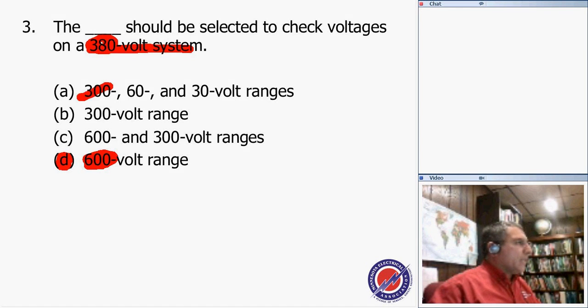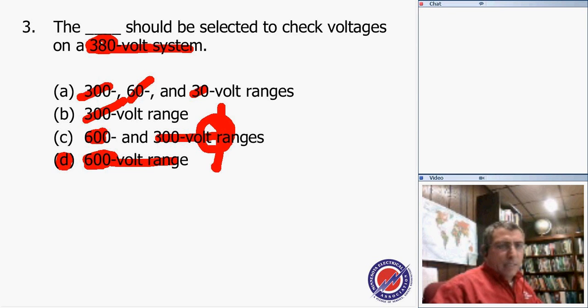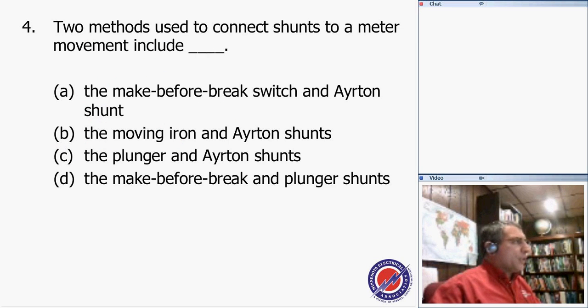So I can't use any of these. I can use this one, but the range that I selected is the wrong range. That's why this is wrong. So the range has to be the 600 volt range. Straightforward. You can't use a voltmeter range that's lower than the voltage that you need to measure. That makes sense, huh?